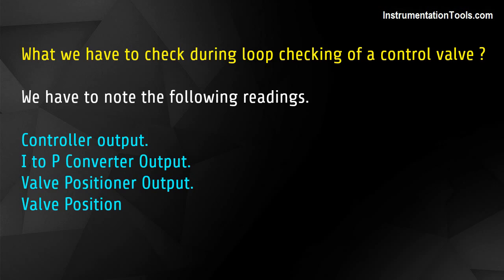What do we have to check during loop checking of a control valve? We have to note the following readings: controller output, I to P converter output, valve positioner output, and valve position.